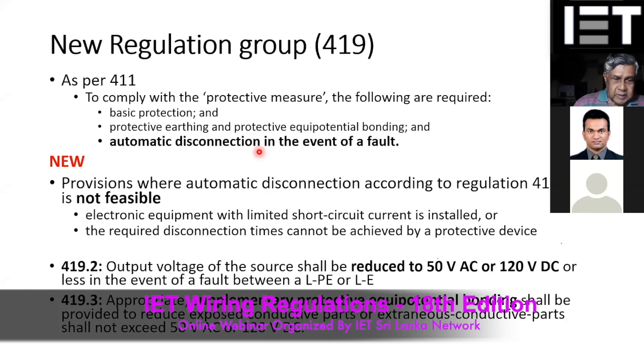So as per the 17th edition, that was the requirement. But later people realized that in the 17th edition, even though it was mentioned as a compulsory requirement, there are a lot of electronic equipment which cannot follow this requirement. Because of that, the new section was added with new regulation numbers, especially for the locations where you cannot apply this, where the disconnection time and the requirements are not feasible. So two new regulations were added: if there is a fault, you have to reduce the supply voltage to less than 50 volts or 120 volts for that type of electronic circuit, or else you have to have supplementary bonding.